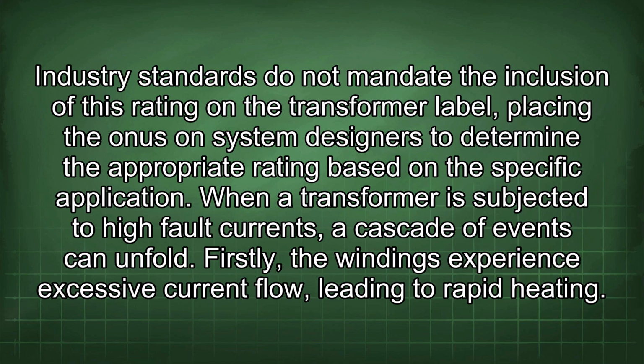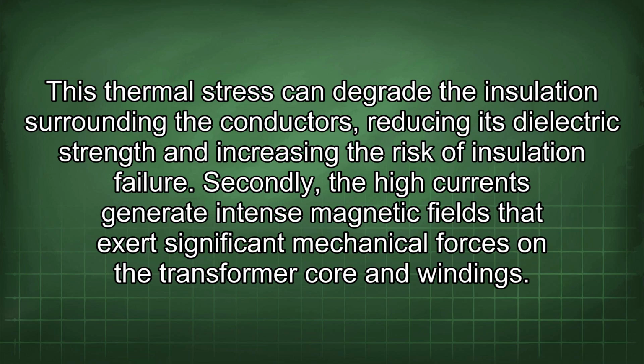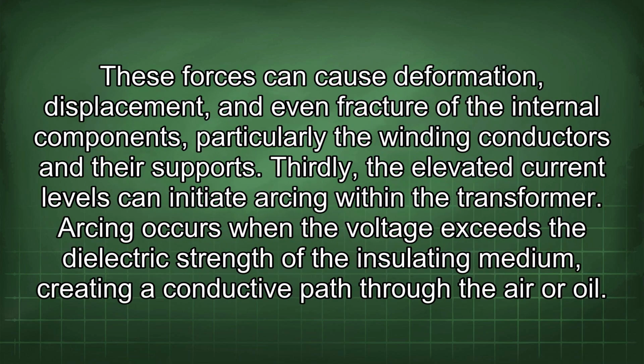When a transformer is subjected to high fault currents, a cascade of events can unfold. Firstly, the windings experience excessive current flow, leading to rapid heating. This thermal stress can degrade the insulation surrounding the conductors, reducing its dielectric strength and increasing the risk of insulation failure. Secondly, the high currents generate intense magnetic fields that exert significant mechanical forces on the transformer core and windings. These forces can cause deformation, displacement, and even fracture of the internal components, particularly the winding conductors and their supports.